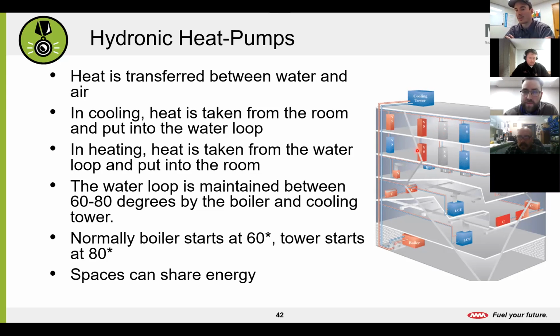But it's actually a very similar principle to VRF in that we can do heating and cooling simultaneously, and we're just transferring heat between the building. The way that works is if you look at any of these units that are in cooling, these blue ones, when you're in cooling, you're absorbing heat from the indoor air, you're putting that into the refrigerant, and that refrigerant is then putting that heat into the water. I'll show you, there's a good diagram coming up next. I'll show you exactly where that takes place. But if we're in cooling mode, we're taking the heat from inside and we're putting it into the water basically.